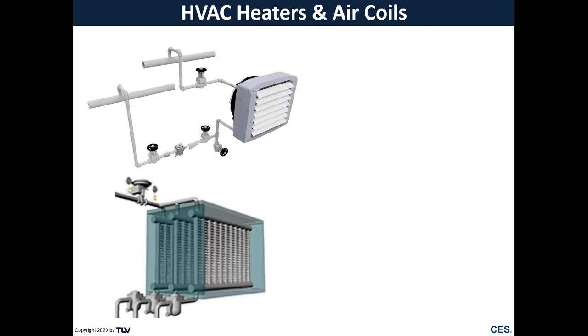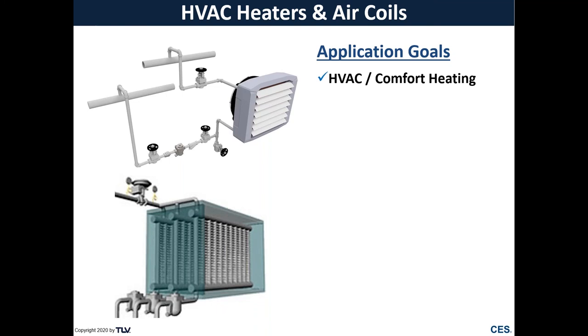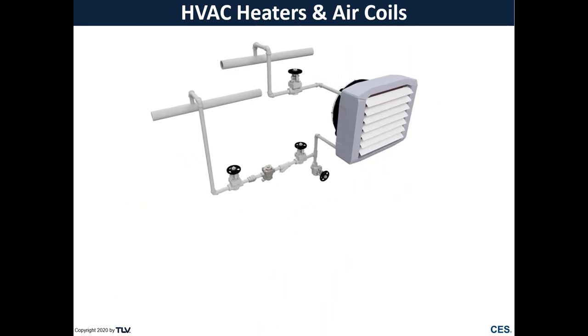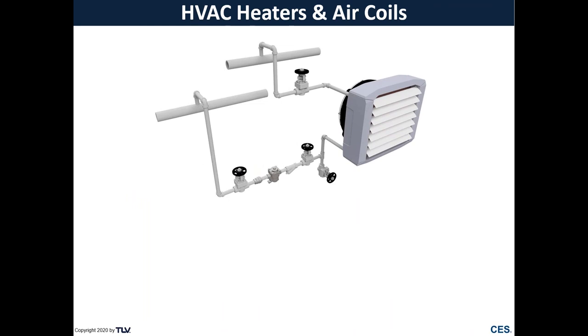All right, moving on from tracing into our process type applications, our HVAC heaters and our air coils. Often these are referred to as unit heaters, comfort heaters, many different names. But basically they're doing some type of heating for personal comfort. And the big goal here is that we want to prevent freeze damage of these coils. So if we back up condensate in this type of coil, we have very cold air in cold climates going across these coils. It could freeze that condensate backed up in those coils and cause damage.